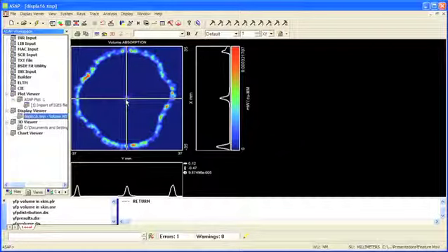In a lot of these applications in the past, there have been problems with creation of fibrosis or scarring on the inside of the bladder, basically turning a non-invasive procedure into an invasive procedure later on when they have to remove the scarring. What we can do is examine the light distribution on the inside of the bladder and compare that to previous simulations where only a spherical bladder was used as an approximation, and determine, based on the structure of the bladder, what the ideal probe shape is in order to get uniform illumination on the interior of the bladder.